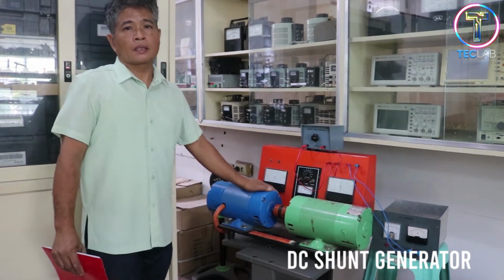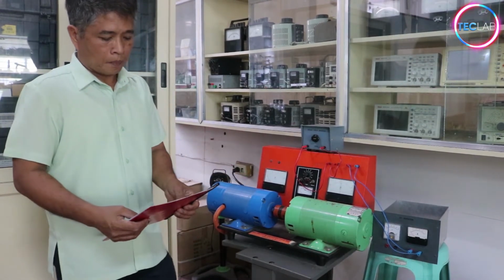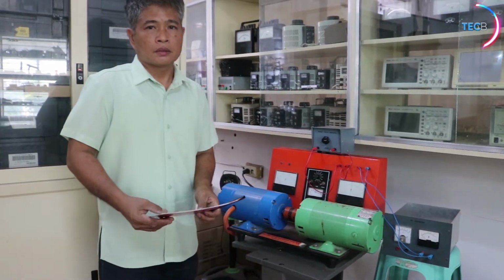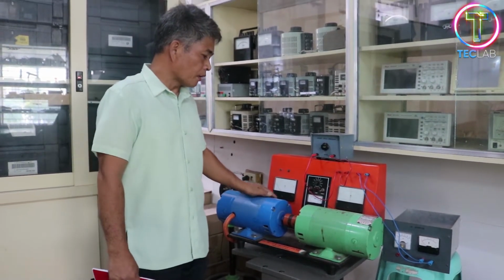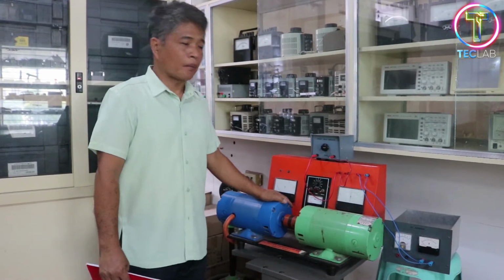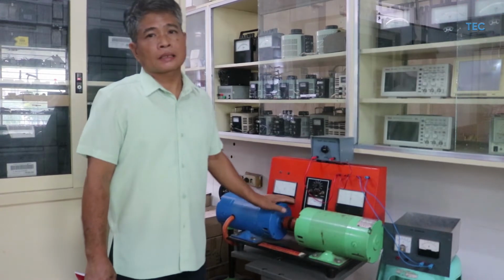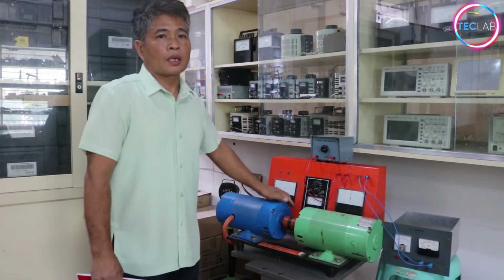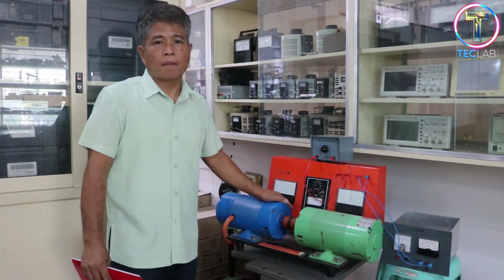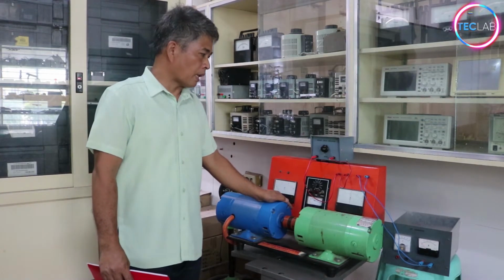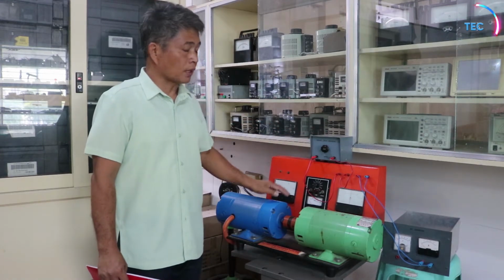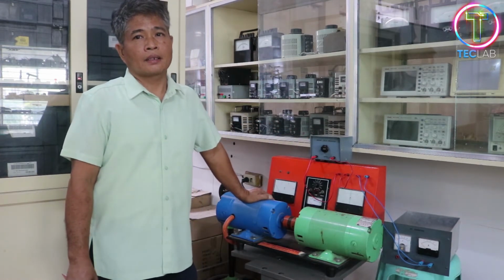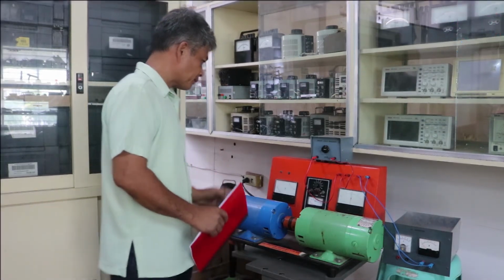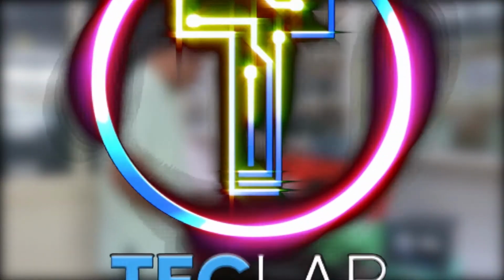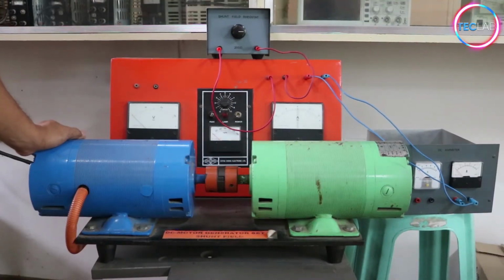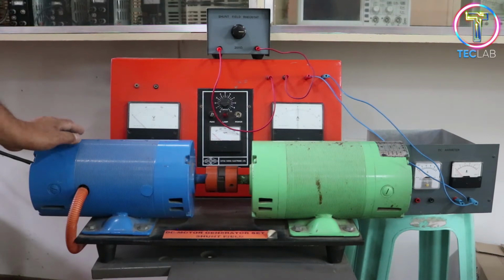Now there are factors affecting the voltage generation of the no-load characteristic of a DC shunt generator. Number one, the speed of the prime mover, and number two, the magnitude of the flux. Now, to demonstrate the magnitude of flux, of course, we cannot directly measure the flux. Instead, we'll be using the field ammeter. Then we will connect this resistor to control the field current. Okay, there are two factors affecting the no-load characteristic of this generator.